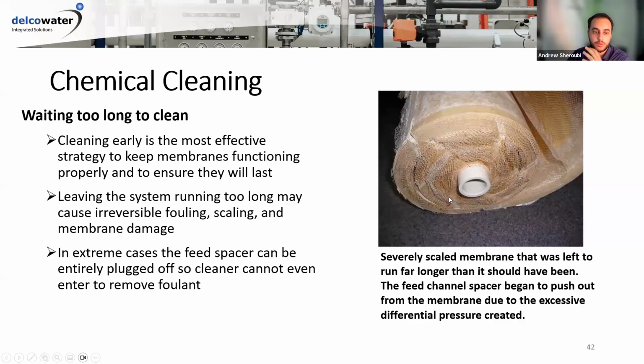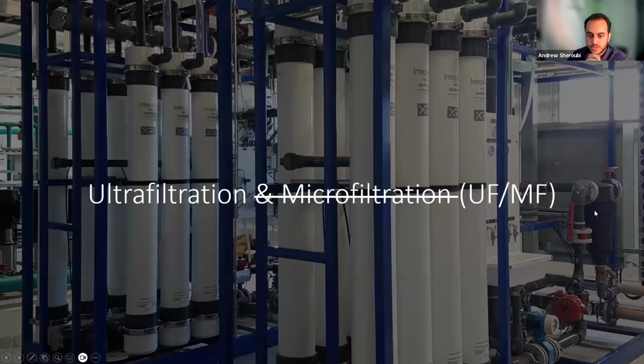But it is the most effective way to keep the membrane functioning, and you do that to prolong the membrane life. I had a client here that didn't do any cleanings, and he was replacing his membranes every 6 months. These are supposed to last 5 years, but he just didn't want to bother with the cleaning process. But it is quite important. And it could even damage the bigger system and kind of not explode, but kind of go out like that.